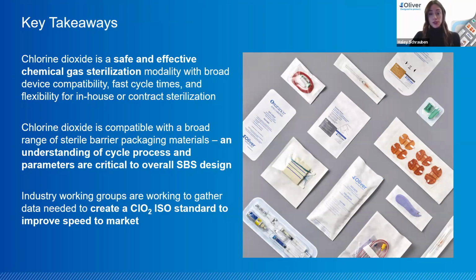With that said, as you saw also from a parameter perspective, it's important that you understand those critical cycle parameters that can impact packaging so that you're ensuring you have an effective design to protect the device, maintain sterile barrier while also getting proper sterilization. And finally, industry working groups are collaborating to collect data that will support standard development, which Emily alluded to a little bit throughout the presentation today. And this will ultimately make it easier for industry to adopt and validate alternative sterilization modalities such as chlorine dioxide and some of the others that we saw at the top of the presentation.